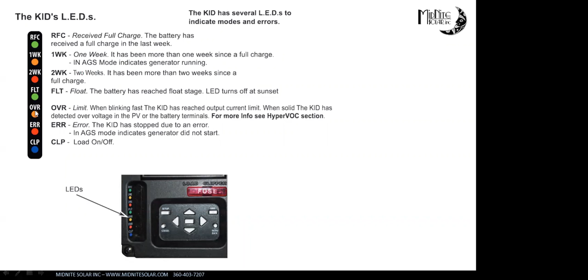As you look over this wiring diagram, all of our charge controllers, be it the Kid, the Brat, the Classic, or the DIY, will tolerate being over PV. They regulate very well, so if you're doing an off-grid system and want extra PV on it for bad days, you can do that on any of these controllers. You just have to be mindful of the voltage—that's really what kills charge controllers, too much voltage.